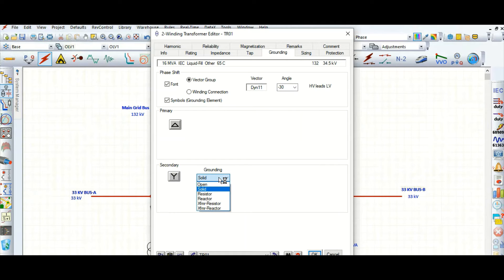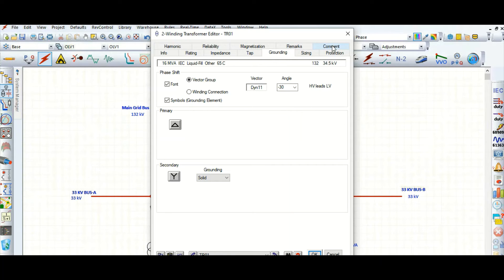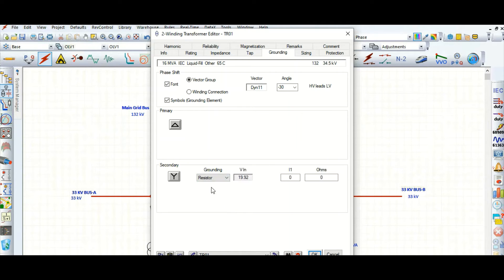Now, coming to the transformer secondary grounding: whether it is solidly grounded, resistance grounded, reactance grounded, or open — you specify it here. This is an MV transformer. Suppose this is resistance grounded, so select the resistor and it will ask for the fault current parameter — what ampere value you want to restrict to.